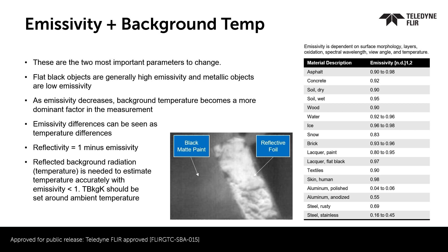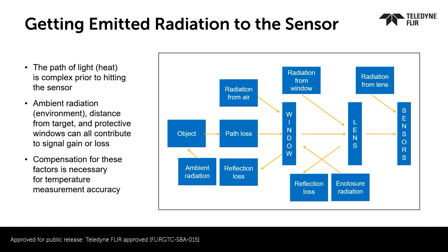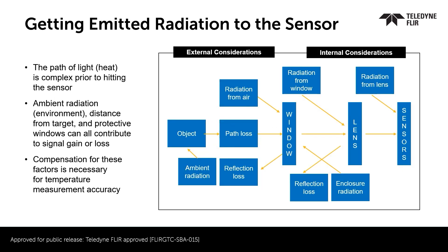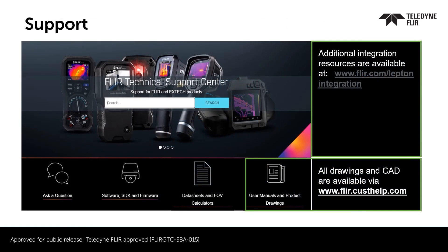The Lepton default emissivity is set equal to 1, so it's best to adjust emissivity using the table shown here. There are external environmental and internal system considerations that impact radiometric accuracy. In addition to the factors introduced in this presentation, it may be useful to explore the thermography training available at the Infrared Training Center. For further questions or support, please go to FLIR.CUSTHELP.COM to connect with our support agents as well as our applications engineers. Additional integration resources can be found at FLIR.COM/LeptonIntegration.